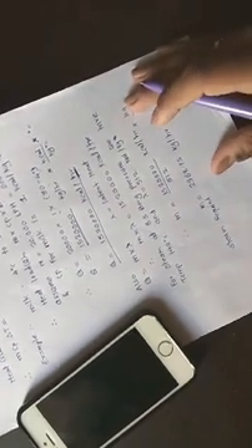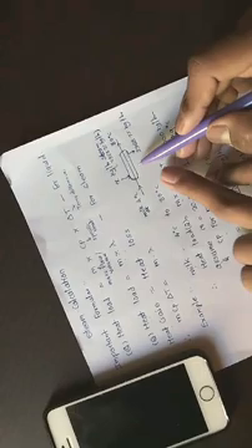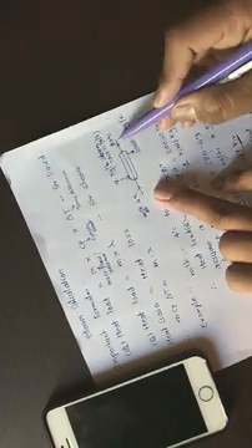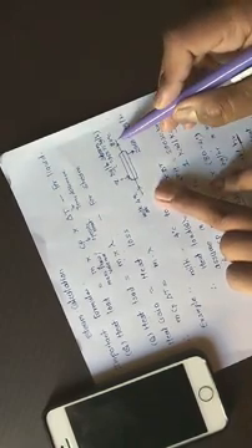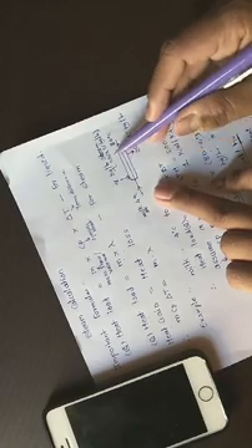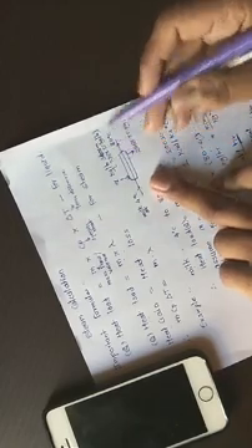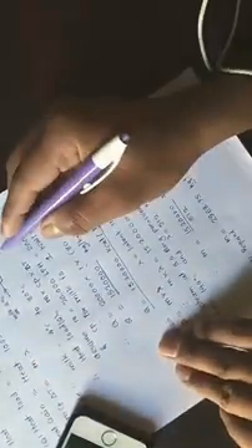By this method you can calculate for a CIP station, and you can do the CIP heater design. So now when we look at our heat exchanger or PHE, when I enter 4 degree Celsius, I will get 80 degree Celsius temperature out. That's why I need this much amount of steam which we have calculated here. So the condensate will be with the same flow rate and the same capacity.